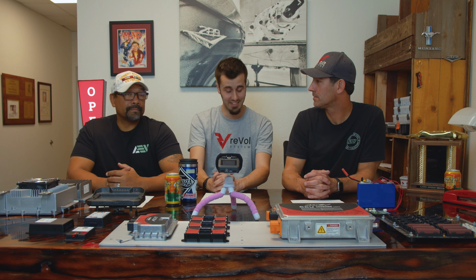But just to go back to alarms, that car you were talking about that I had, which was distinctly second-hand as an EV conversion, you're talking about its state of charge. It had a state of charge gauge, it had a voltage gauge. But that's not the whole story, because one cell group in that whole pack was negative. Every time it was charged, it was getting dragged up to 5 volts past everything else, and on discharge it was so weak it got pushed negative. So as far as I knew, everything was running great because my state of charge looked fine, but it didn't have a battery management system, which would have told me the state of health. It did not tell me the state of health.